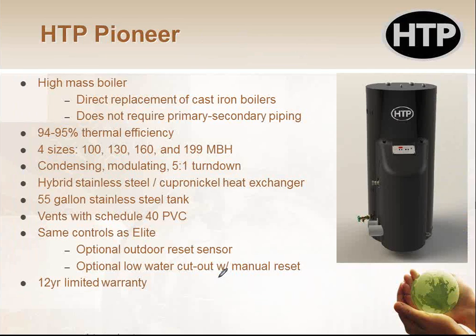One of the other things we do is sometimes we will recommend that you do not use a low mass boiler. Sometimes there's reasons to do that. There's usually two reasons. One is on a small residential plant where you've got a 100, 150,000 BTU boiler or something like that, and you don't want to change all the piping around and add the second pipe. We might recommend using a high mass, high efficiency boiler. There's several different types of that, and I'll show you two or three of them right now. So I can get away from having to do the primary and secondary piping. Still get high efficiency, still get a condensing boiler, still modulating, still good turn down, still outside air reset controls, all that stuff.